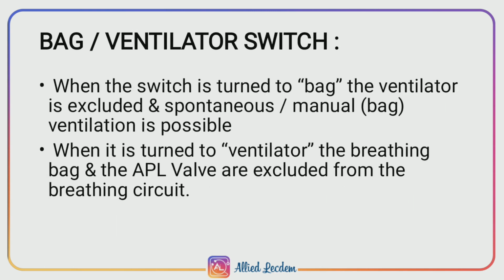Bag ventilator switch. Whenever a ventilator is used on an anesthesia machine, the APL valve must be functionally removed or isolated from the circuit. A bag or ventilator switch generally accomplishes this. There are two options. One is bag, which is manual ventilation. The other is mechanical ventilation, which is provided to the patient. When the switch is turned to bag, then manual or spontaneous ventilation is possible. The anesthesiologist will be squeezing the breathing bag at a set interval of time.